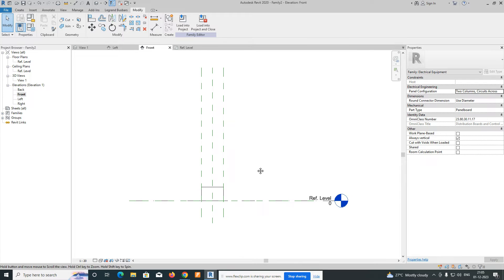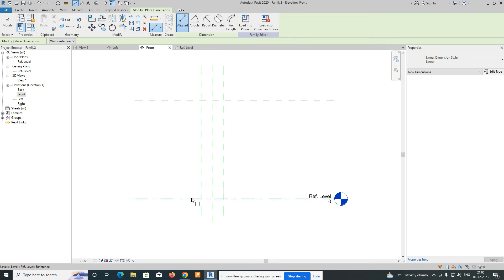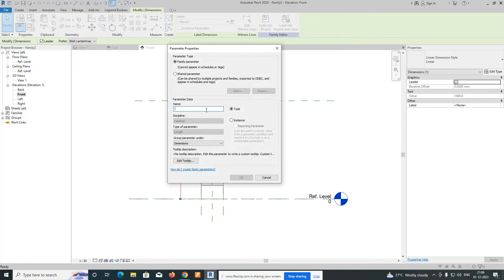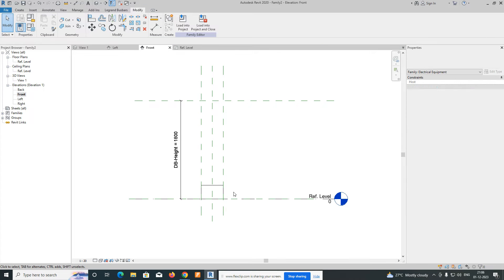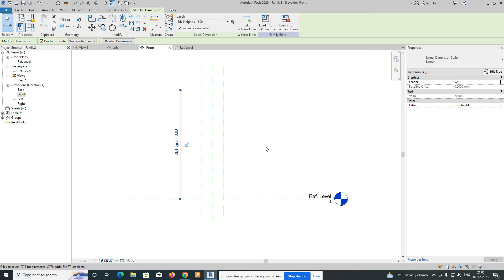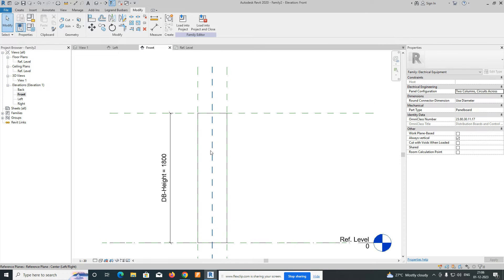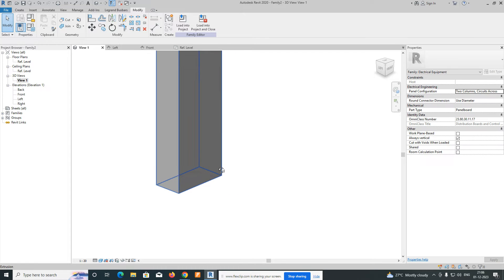Go to the front view. We need to give the panel a height. Go to Create, Reference Plane, and give an offset of 1800. Pick the line. Then add a dimension and assign a parameter named 'DB Height' as an instance parameter, and click OK. Use the Align tool to align the top of the extrusion to this reference plane. If you change the value to 2000 or 1500, it adjusts automatically. I'm keeping it at 1800.